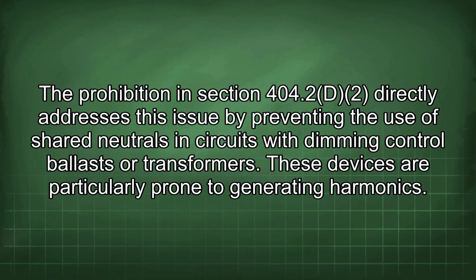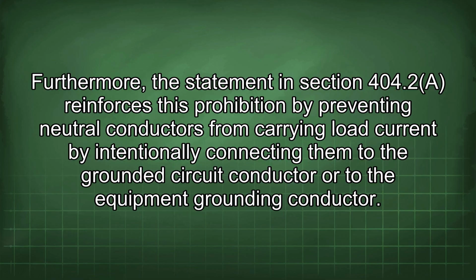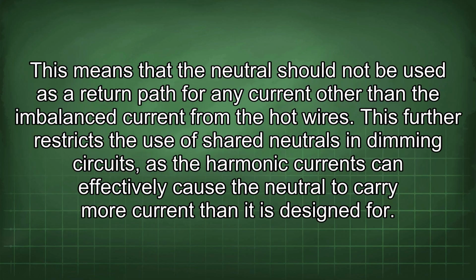The prohibition in Section 404.2 directly addresses this issue by preventing the use of shared neutrals in circuits with dimming control ballasts or transformers. These devices are particularly prone to generating harmonics. Furthermore, the statement in Section 404.2 reinforces this prohibition by preventing neutral conductors from carrying load current by intentionally connecting them to the grounded circuit conductor or to the equipment grounding conductor. This means that the neutral should not be used as a return path for any current other than the imbalanced current from the hot wires. This further restricts the use of shared neutrals in dimming circuits, as the harmonic currents can effectively cause the neutral to carry more current than it is designed for.